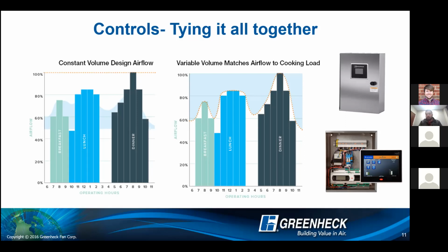Now, the next big thing in the market is variable volume. Variable volume, just energy consumption, is kind of the wave of the future. From a cost perspective, these have come much closer in recent years. The price between a constant volume system and a variable volume system has reduced drastically. This is mainly driven by the fact that Greenheck and ECM direct drive motors, those ECM motors, so our very green motors, don't require VFDs. They just need a 0 to 10 VDC signal. So we've eliminated the VFD from the variable volume, thus eliminating a lot of cost.